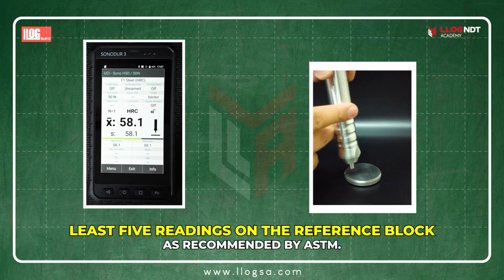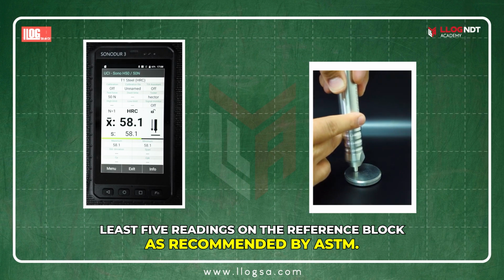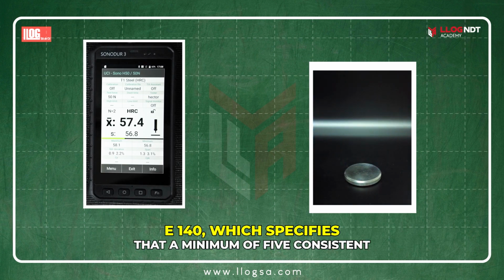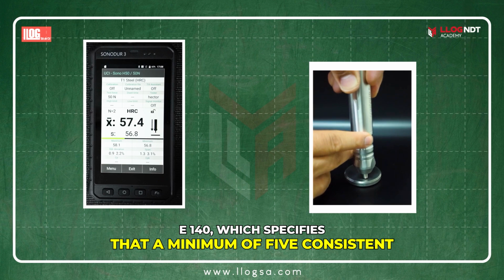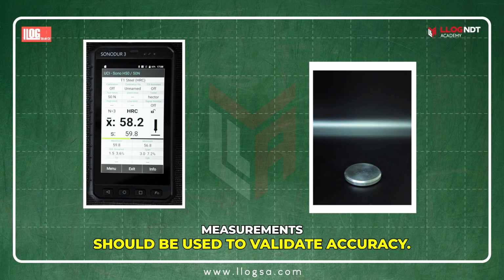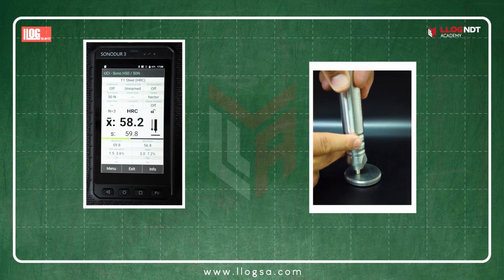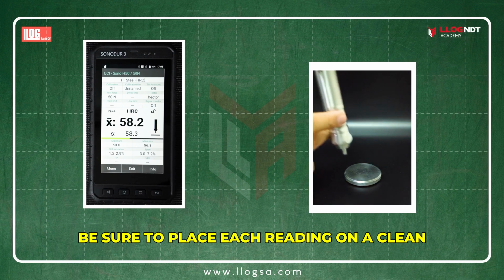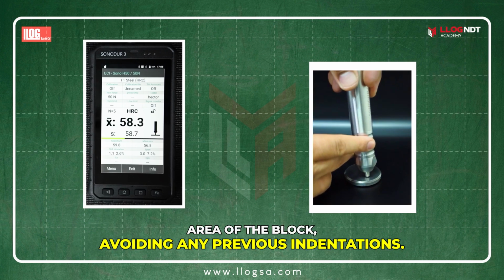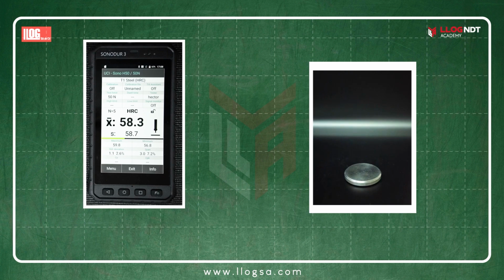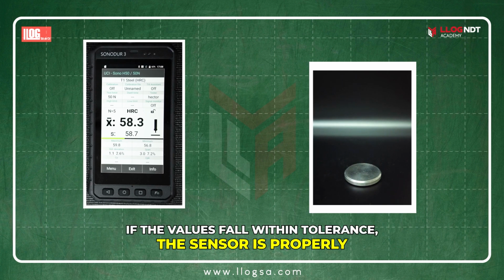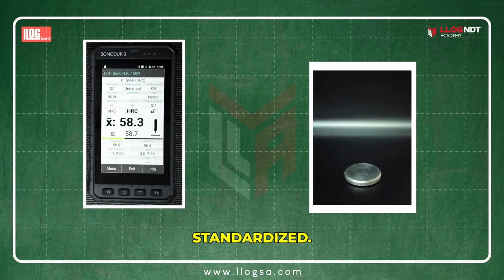Take at least 5 readings on the reference block as recommended by ASTM E140, which specifies that a minimum of 5 consistent measurements should be used to validate accuracy. Be sure to place each reading on a clean area of the block, avoiding any previous indentations. If the values fall within tolerance, the sensor is properly standardized.